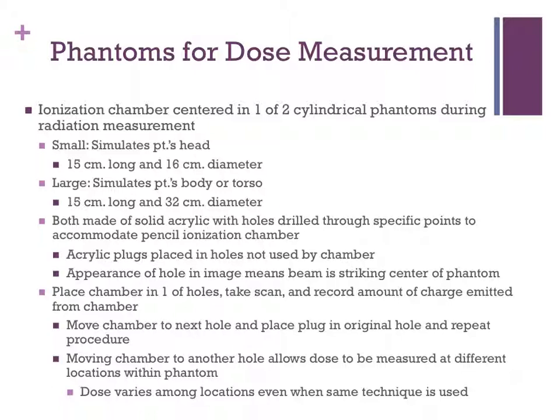Moving the chamber to another hole allows the dose to be determined at a variety of locations within the phantom. Generally, the dose varies among locations, even when the same dose technique is used, so it's necessary to measure the dose at several locations for a given technique.